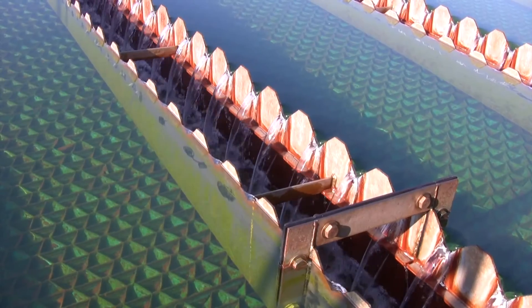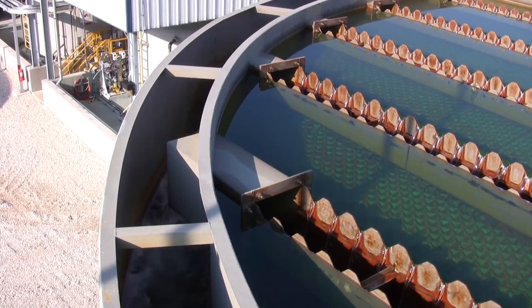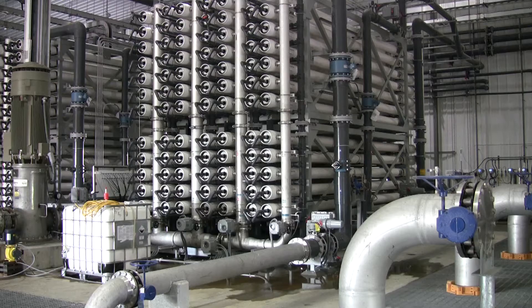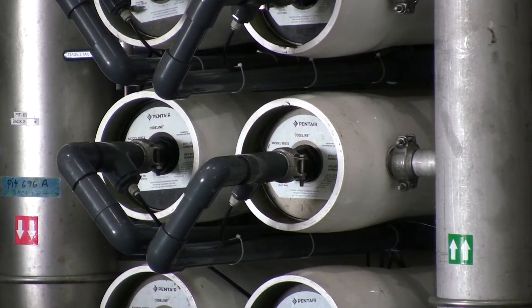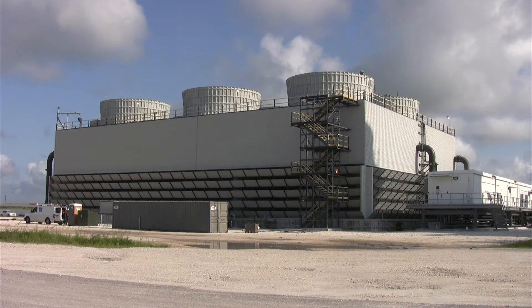The water then passes through this system into a Greenleaf multimedia filtration system. From there, that water is transferred over to our RO, or reverse osmosis system. This is an 85% recovery system creating a very high quality permeate used for reservoir makeup and for cooling tower makeup.